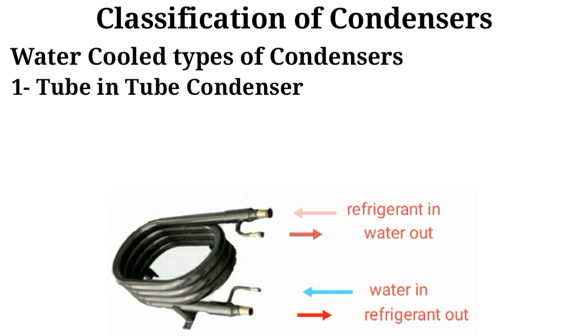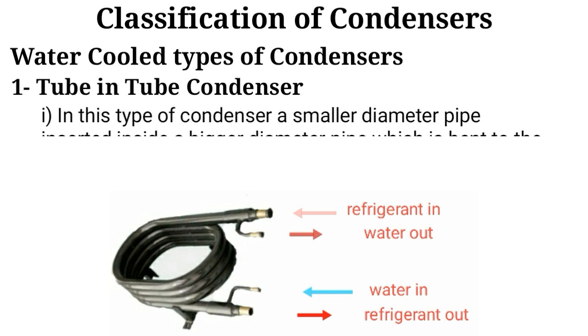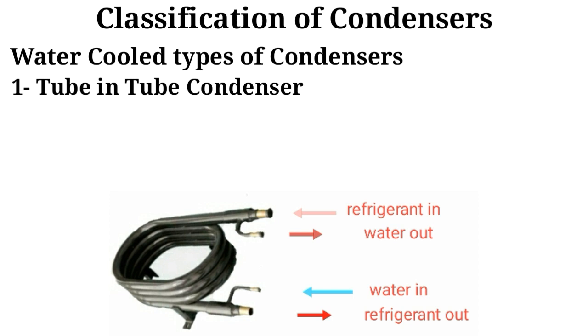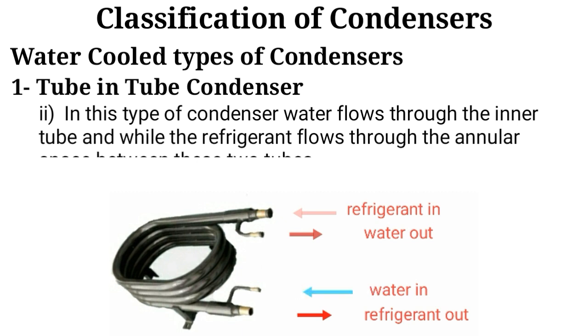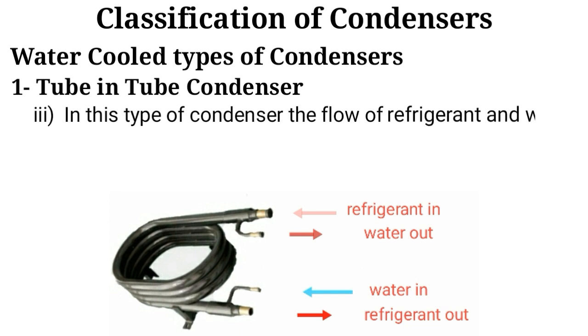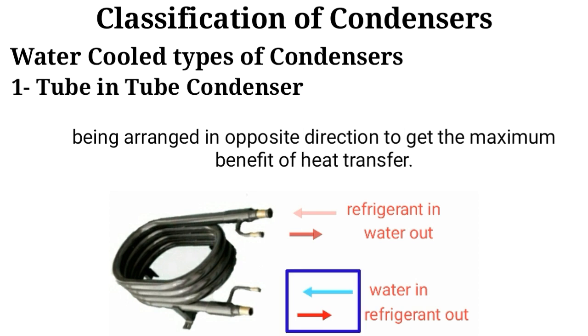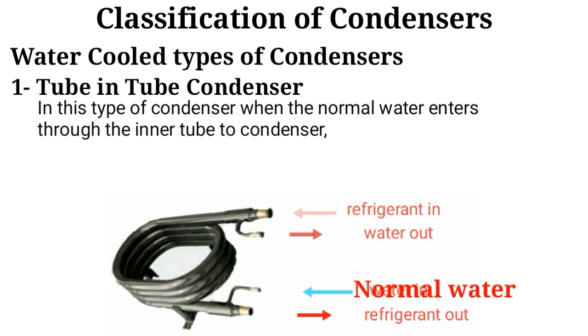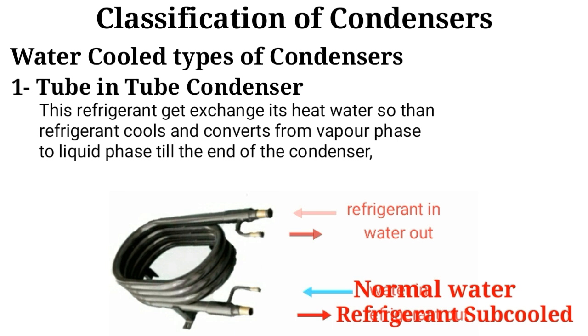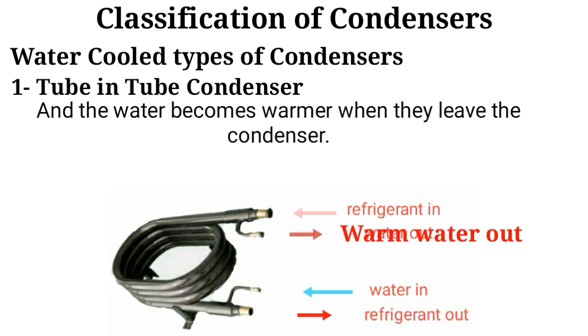In the tube-in-tube type condenser, a smaller diameter pipe is inserted inside a bigger diameter pipe, which is bent to the desired form. Water flows through the inner tube while the refrigerant flows through the annular space between the two tubes. The flow of refrigerant and water is arranged in opposite directions to get maximum benefit of heat transfer. When normal water enters through the inner tube, the refrigerant exchanges its heat to the water, cools, and converts from vapor phase to liquid phase by the end of the condenser, while the water becomes warmer as it leaves.